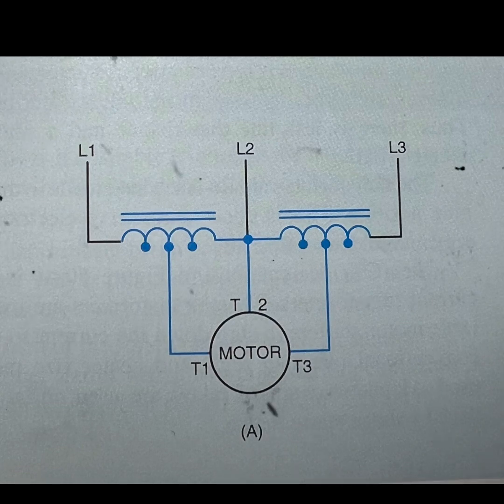Most motors are successfully started at 65% of line voltage. In situations where this value of voltage does not provide sufficient starting torque, the 80% tap is available. If the 65% starting voltage creates excessive line drop to the motor, the 50% taps are available. This way of changing the starting voltage is not usually available with other types of starters. The starting transformers are inductive loads, therefore they momentarily affect the power factor. They are suitable for long starting periods.